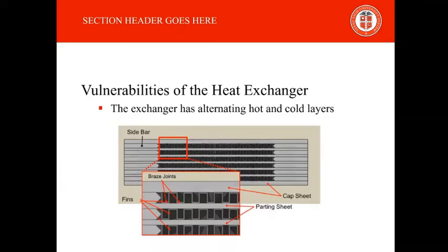In general, the brazed aluminum heat exchanger is a device that allows heat transfer from a hot process stream to a cold one. The BAHX does this by a series of alternating hot and cold layers separated by parting sheets. Inside these layers, there are corrugated fins and sidebars to seal the fluid inside. These layers are collectively called the core of the BAHX, and the outer layers are sealed with cap sheets, which are thicker than the parting sheets.